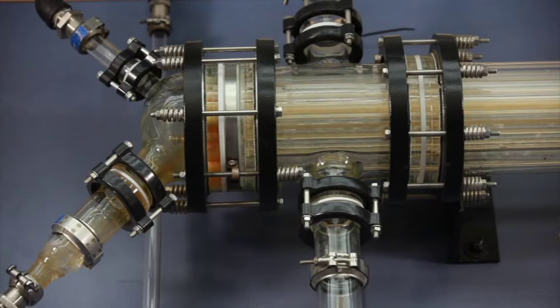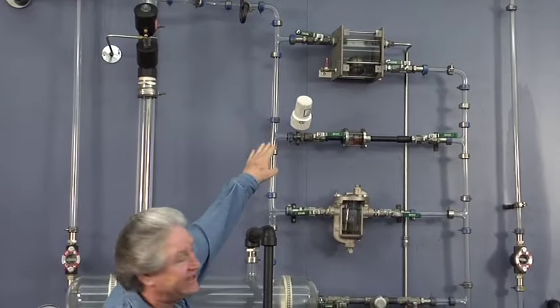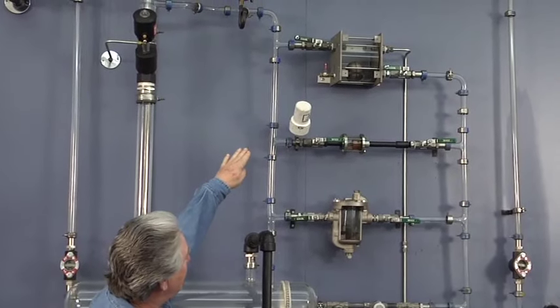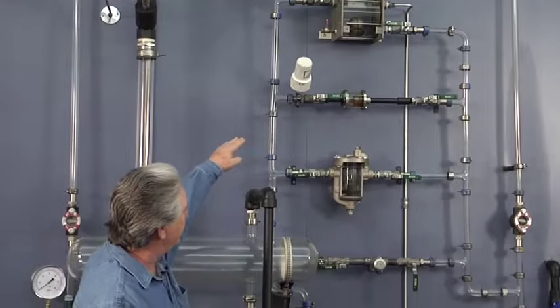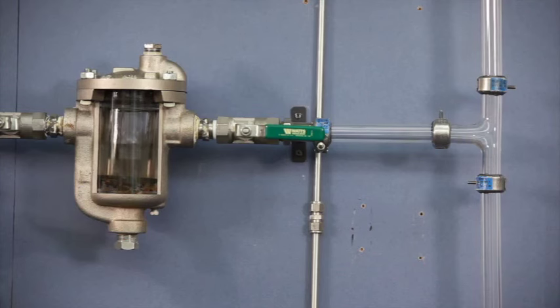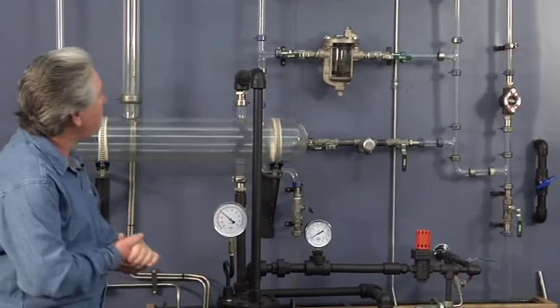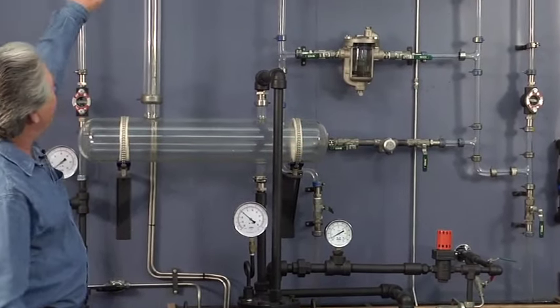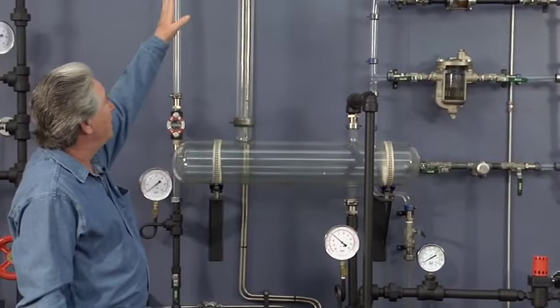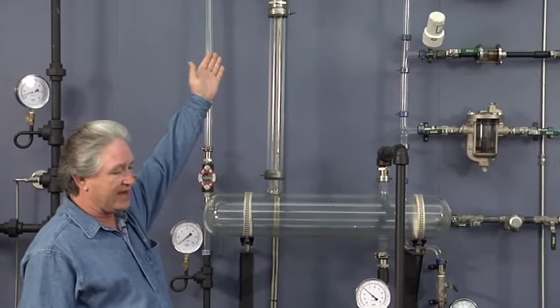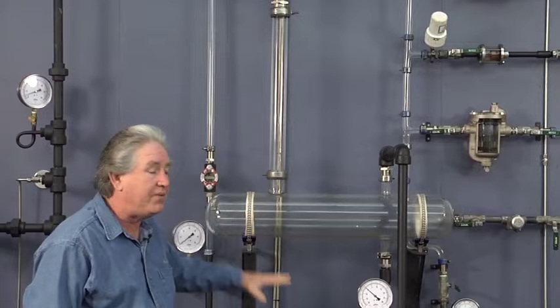The scenario that we're simulating right now goes strictly from the exchanger to some type of steam trap, whether that be an F&T trap at the top, a thermostatic trap in the middle, the IB trap, or at the bottom, an orifice type trap. We also have the ability in this system to open another motorized valve that allows us to feed our pumping trap system.